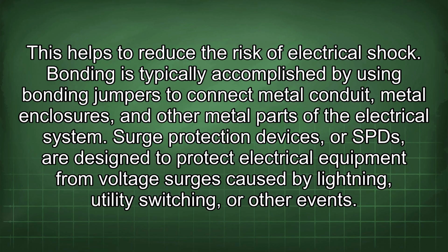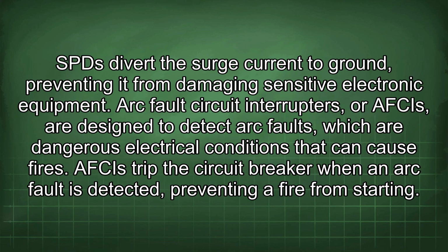Bonding is typically accomplished by using bonding jumpers to connect metal conduit, metal enclosures, and other metal parts of the electrical system. Surge protection devices, or SPDs, are designed to protect electrical equipment from voltage surges caused by lightning, utility switching, or other events. SPDs divert the surge current to ground, preventing it from damaging sensitive electronic equipment. Arc fault circuit interrupters, or AFCIs, are designed to detect arc faults, which are dangerous electrical conditions that can cause fires. AFCIs trip the circuit breaker when an arc fault is detected, preventing a fire from starting.